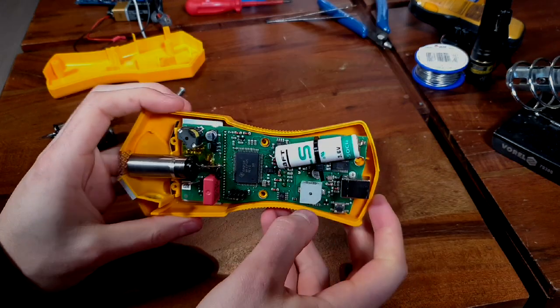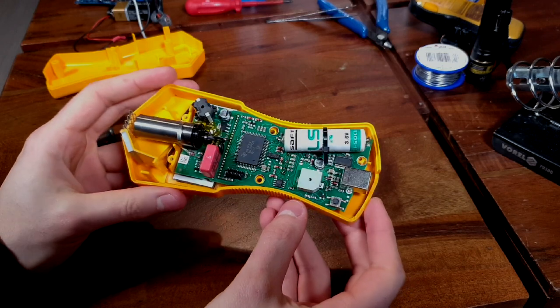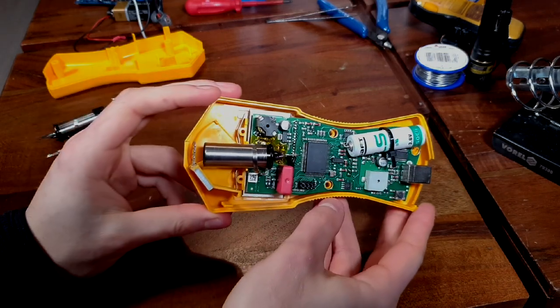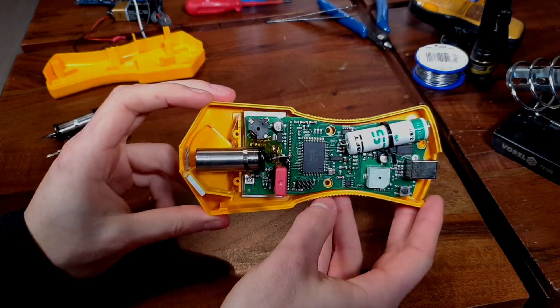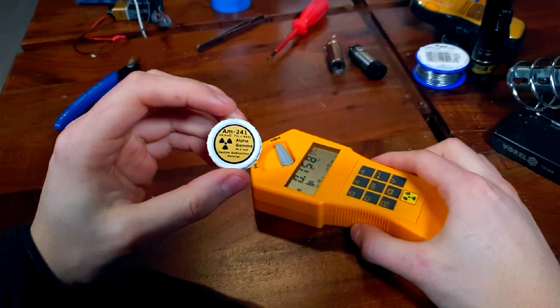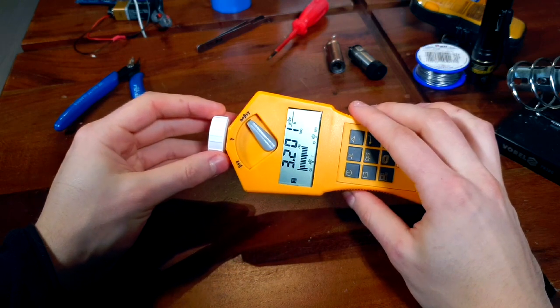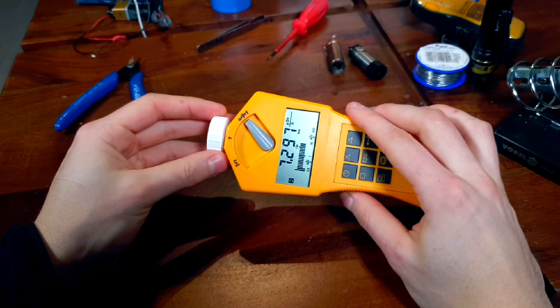One small design issue that I noticed with the Gamma-Scout is that the GM tube is slightly pushed back into the meter. This means that detecting alpha particles will be more difficult, since they have a very small range. What I really like about this meter is that it can detect alpha, beta, and gamma radiation, and it shows readings in those units as well as raw activity.